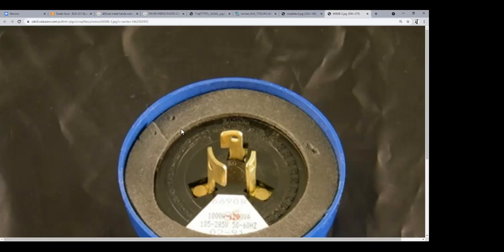Right. We had some, we got away from it back in the day also, of series lighting circuits. So a series lighting circuit would be one photo control controlling multiple lights down a street. Well, if you hang 5 400-watt street lights, that's 2,000 watts, and one photo control couldn't handle it. So that's why we went to full headlights, the photocell on the head of all of our lights.